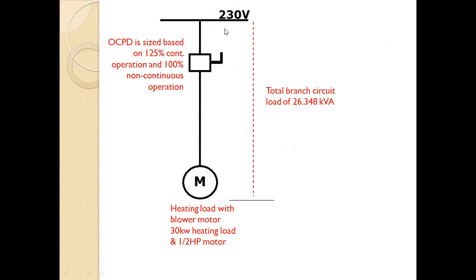For this example, from the source up to the motor, we have a complete circuit. The OCPD is sized based on 125% for continuous operation and 100% for non-continuous operation. The total branch circuit load or total connected load is 26.35 kVA. This is composed of the heating load with blower motor: the 30 kilowatt heating load and the 1/2 horsepower motor.